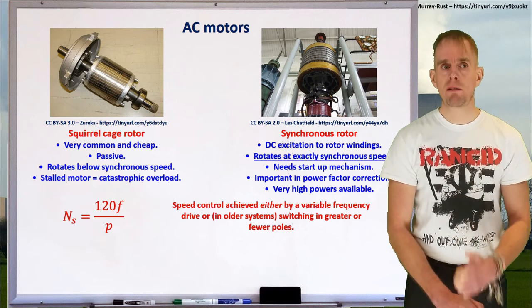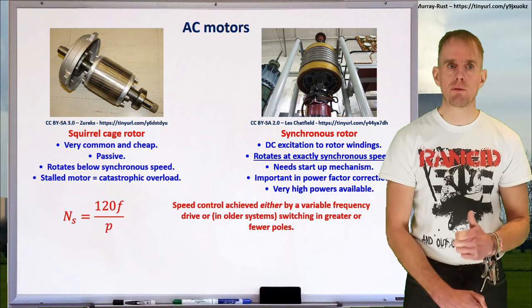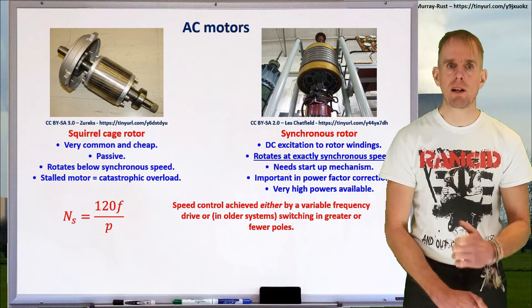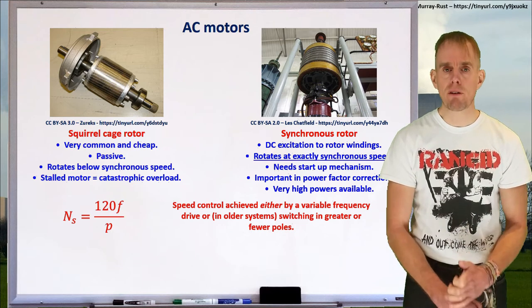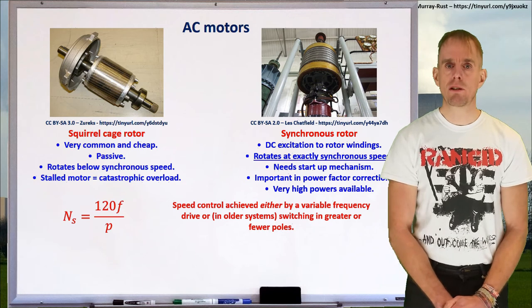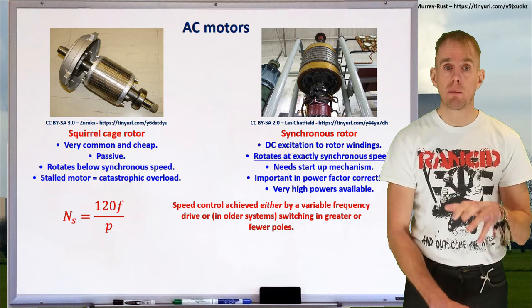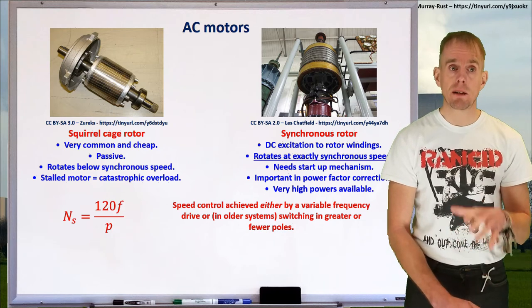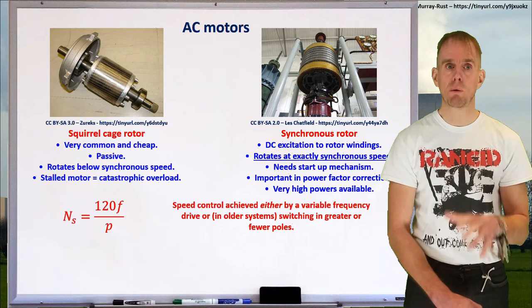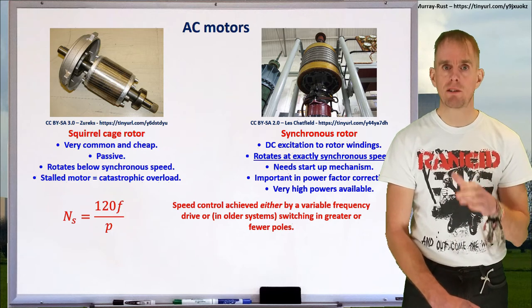The thing to always bear in mind about altering the supply frequency is very often you're having to deliver very high currents to these devices at very high voltage, and so the electronics underpinning your variable frequency drive requires some very high power semiconductors. And so that is why, up until only very recently, typically you've had to switch in and switch out poles and just cope with one fixed synchronous speed.